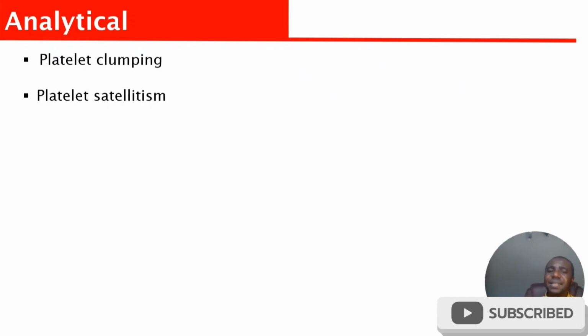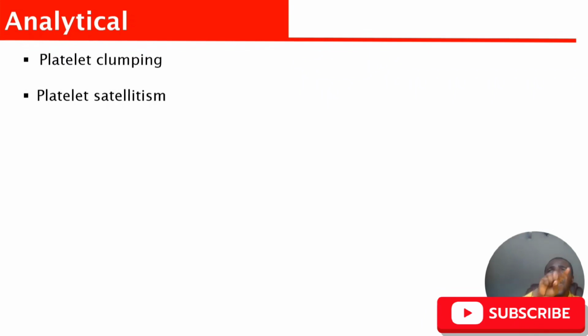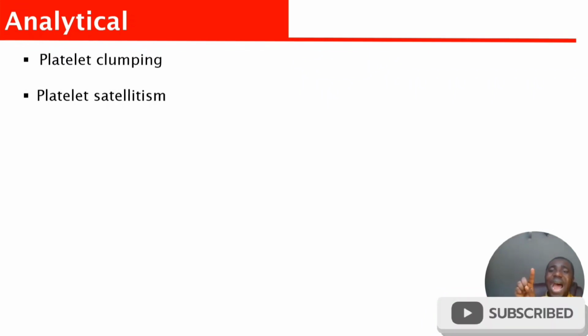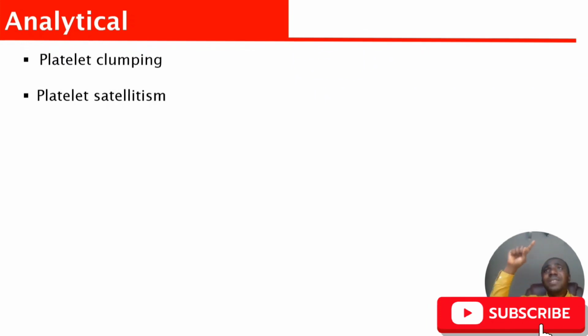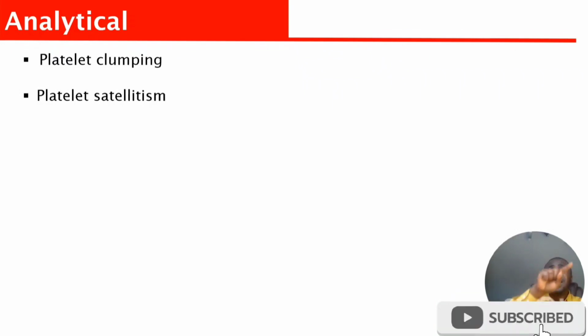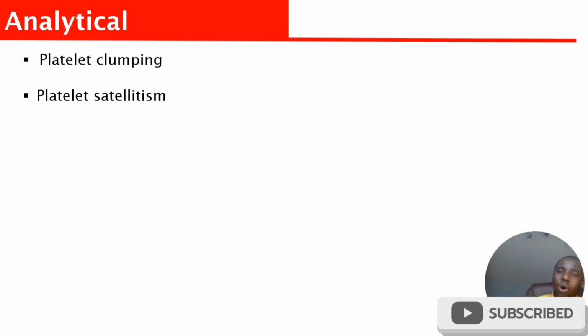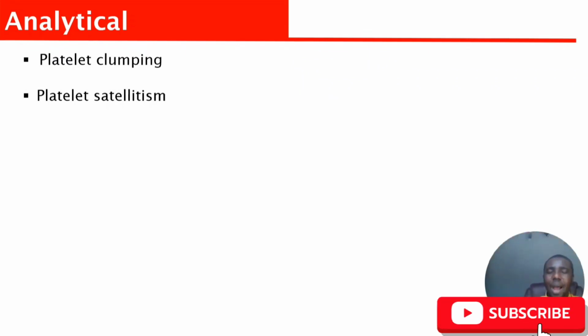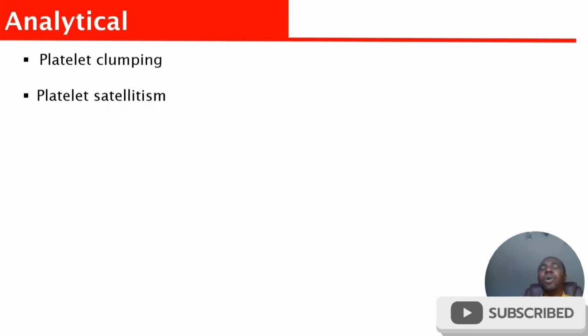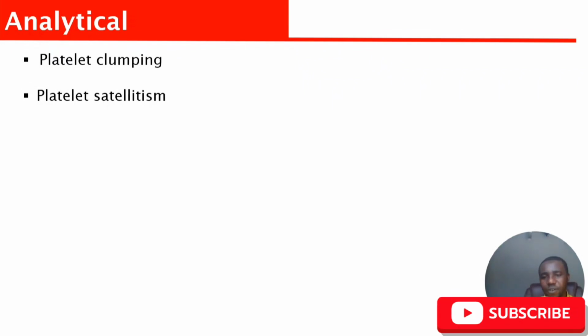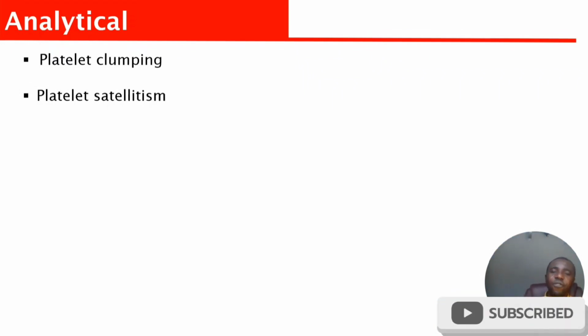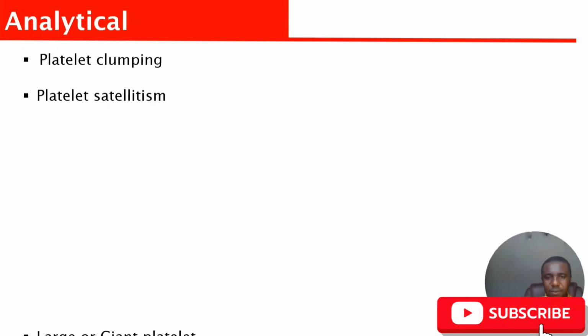But in platelet satellitism, what happens is that you will see platelets surrounding the surface, the membrane of the neutrophils. And I'm going to show you the picture. Once the platelets surround the membrane or the side of the neutrophils, as the neutrophils pass through the aperture, the platelets will also pass through that aperture, and that way the analyzer will be unable to count those platelets because they are going through the aperture with the neutrophils. I hope that makes sense. So that can give a false low platelet count result.